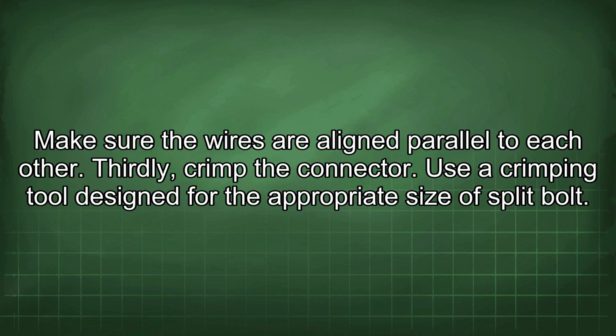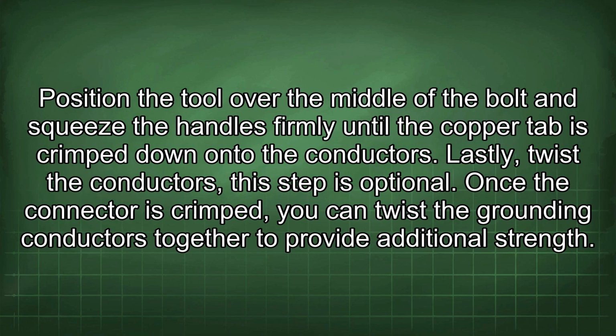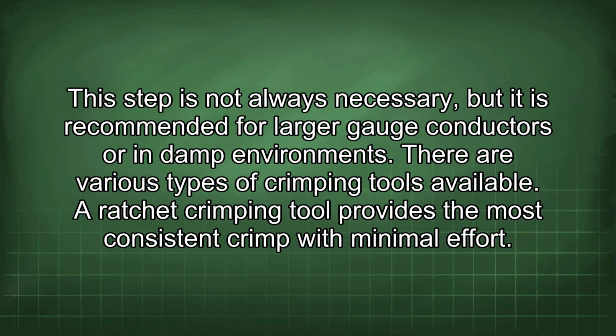Thirdly, crimp the connector. Use a crimping tool designed for the appropriate size of split bolt. Position the tool over the middle of the bolt and squeeze the handles firmly until the copper tab is crimped down onto the conductors. Lastly, twist the conductors. This step is optional. Once the connector is crimped, you can twist the grounding conductors together to provide additional strength. This step is not always necessary, but it is recommended for larger gauge conductors or in damp environments.